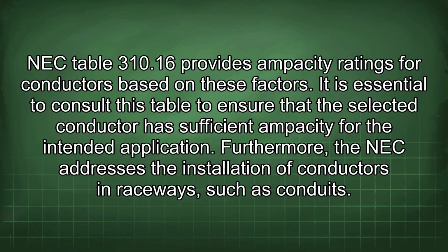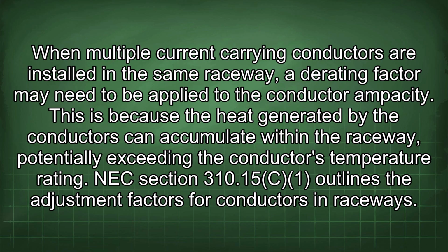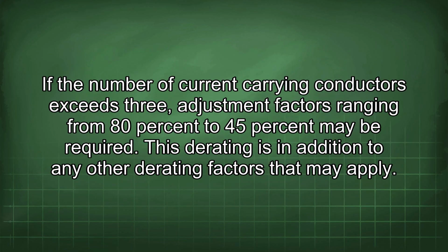Furthermore, the NEC addresses the installation of conductors in raceways such as conduits. When multiple current-carrying conductors are installed in the same raceway, a derating factor may need to be applied to the conductor ampacity. This is because the heat generated by the conductors can accumulate within the raceway, potentially exceeding the conductor's temperature rating. NEC section 310.15 outlines the adjustment factors for conductors in raceways. If the number of current-carrying conductors exceeds 3, adjustment factors ranging from 80% to 45% may be required. This derating is in addition to any other derating factors that may apply.